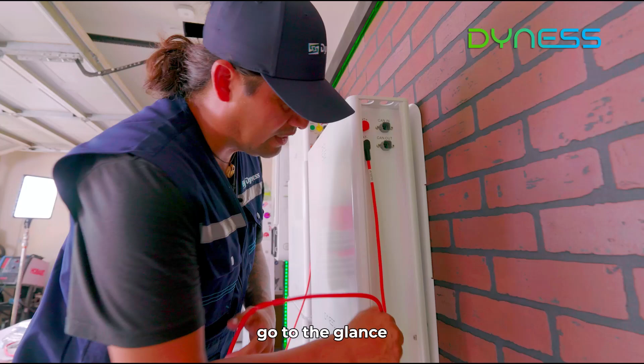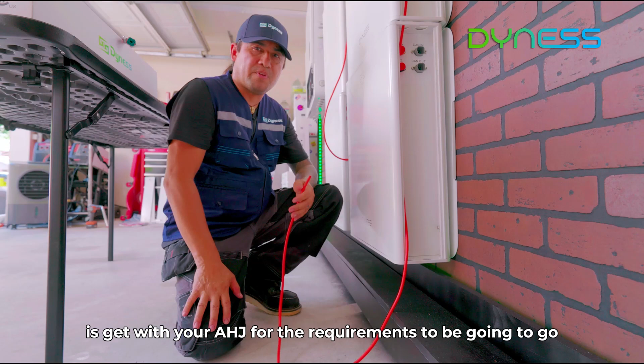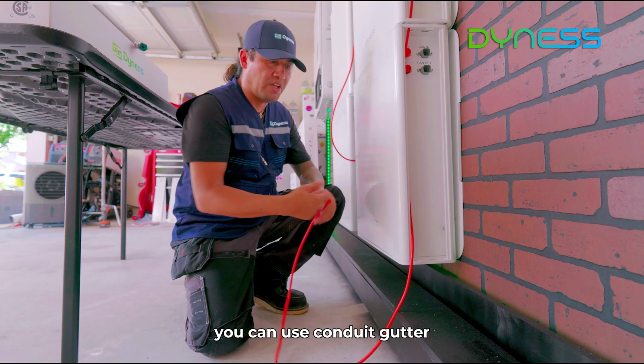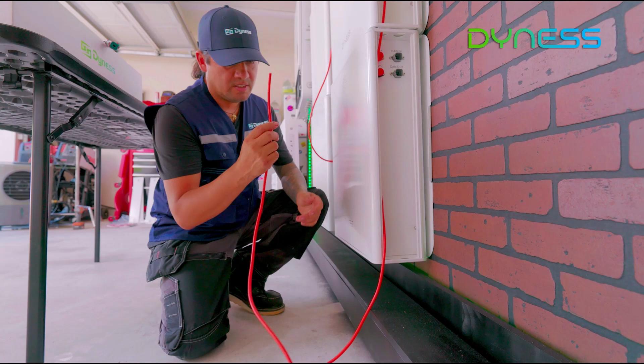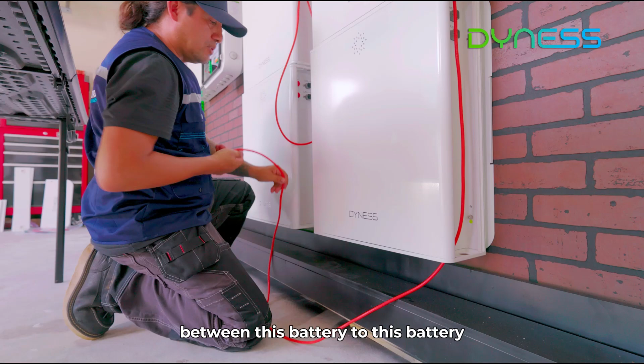Go to the glands for this next installation. What you want to do is check with your AHJ for the requirements between 2 individual batteries. You can use conduit or gutter—make sure your applications are rated for outside and inside use. Just so you can see, we're going to take this through, and you'll have some kind of protection of your choice while doing the installation between this battery and the next.